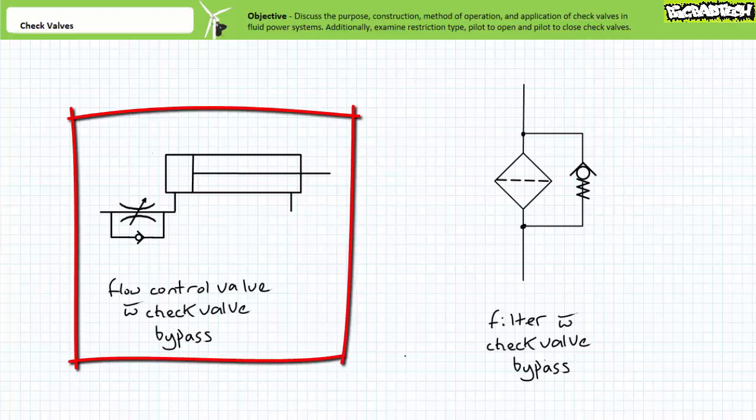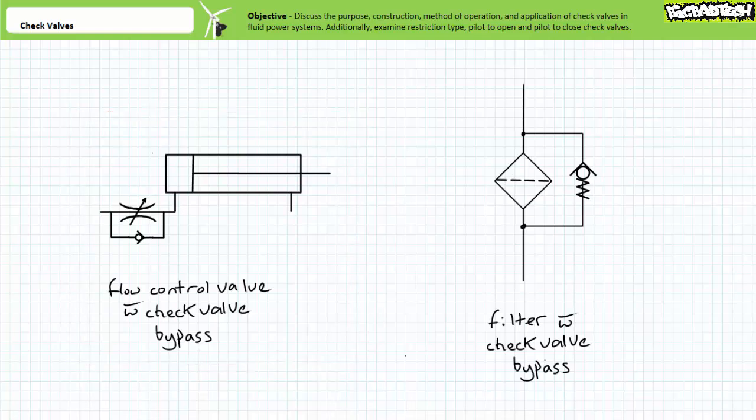Consider a variable flow control valve with check valve bypass on the cap end of a double acting cylinder. In this application and orientation, the check valve bypass allows the flow control valve to restrict flow traveling to the cap end and thereby limit the extension speed of the rod.